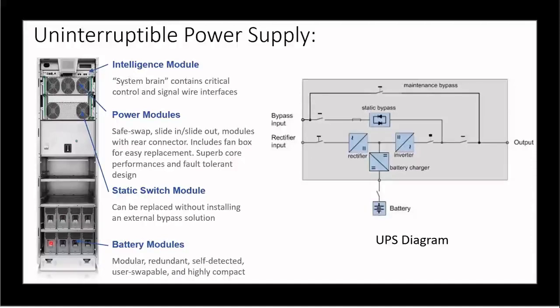So this is a string. One string has 4 modules. This is the space if a customer wants to add more batteries. With this amount of batteries, a customer can get 5 to 10 minutes of runtime, and then they can switch on to the generator. But if they want more runtime, they can add more batteries here. They can also add different battery racks, like on the right side or left side, so it becomes a cabinet full of these battery cabinets. They can do that too.